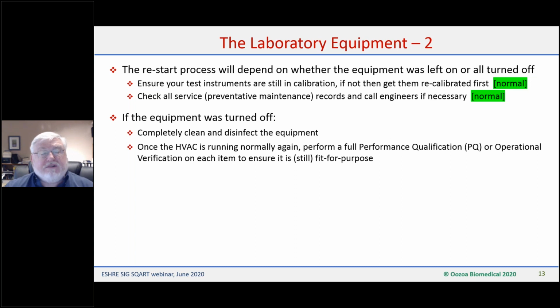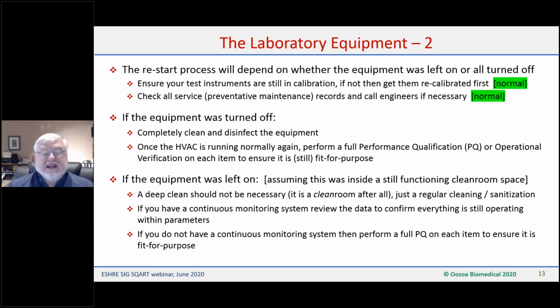If the equipment was turned off, you need to completely clean and disinfect the equipment. Once the HVAC is then running again, you need to do a full performance qualification or operational verification on each piece of equipment to make sure that it is fit for purpose, or still fit for purpose. If the equipment was left on, and I'm assuming here it was inside a still functioning clean room space, a deep clean should not be necessary. Not just the room is clean, so the equipment should still be clean as well. Just a regular cleaning and sanitization as you do in your normal routine practice.